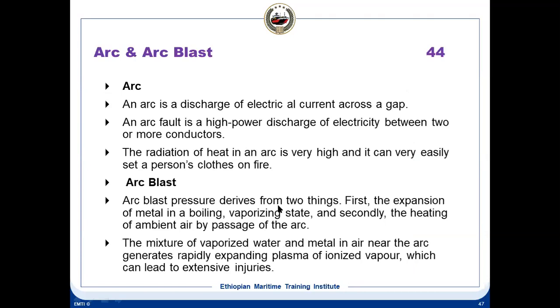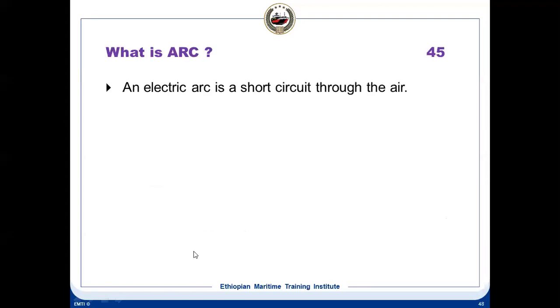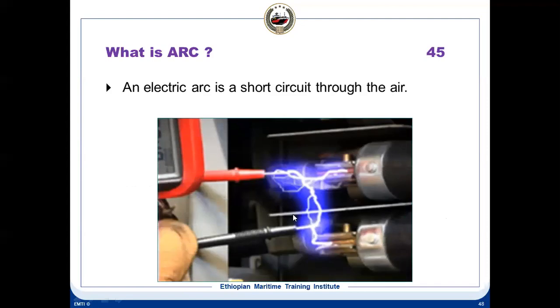Arc blast pressure derives from 2 things. First, the expansion of the metal in the boiling, vaporization state. Secondly, the heating of ambient air by passage of the arc. Mixed vaporized water and metal in the air near the arc generates a rapidly expanding plasma of ionized vapor, which can lead to extensive injuries. So first is an arc. An electric arc is a short circuit through the air. Like when you open a breaker also, you'll find an electric arc. It's a short circuit through the air.